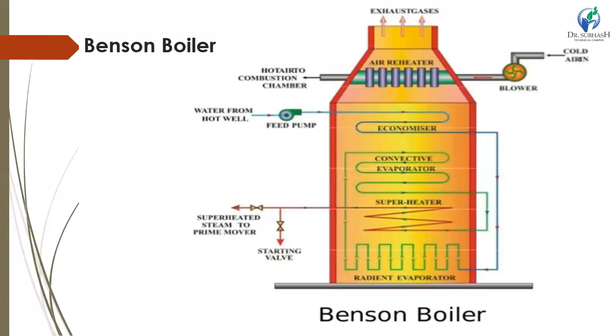Now we will see some disadvantages of this boiler. If distilled water is not used, heavy deposits of salt occur in the evaporator. Hence, the evaporator has to be flushed after every 4,000 working hours to remove salt. Tubes get overheated due to salt deposition, which may result in tube failure. So it can fail the tubes or overheat the tubes.